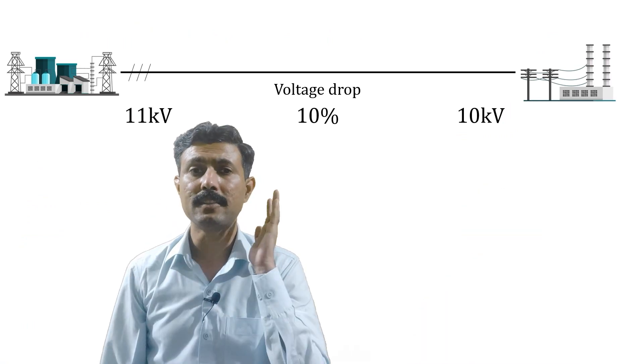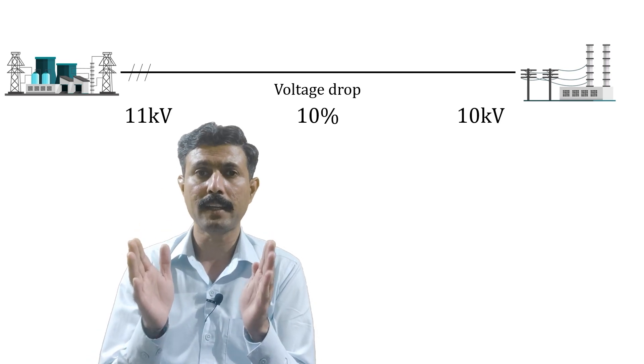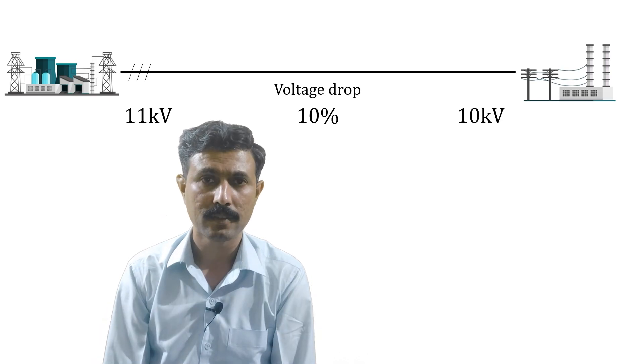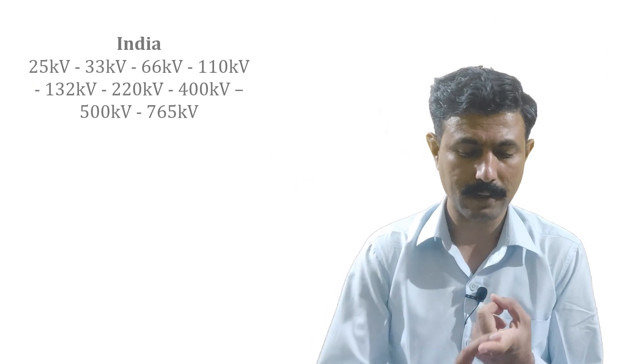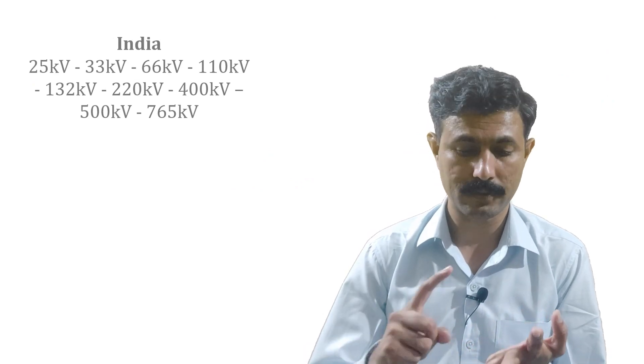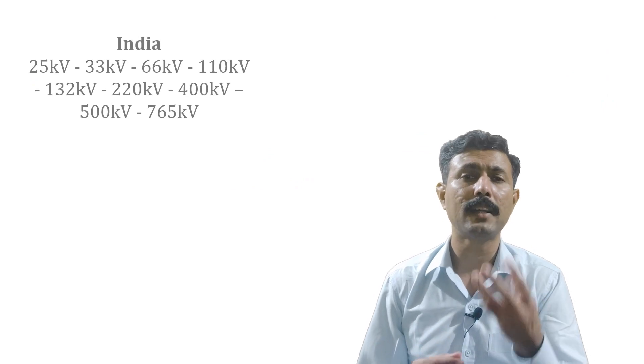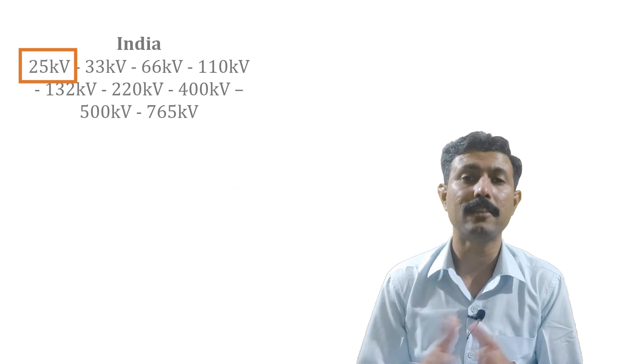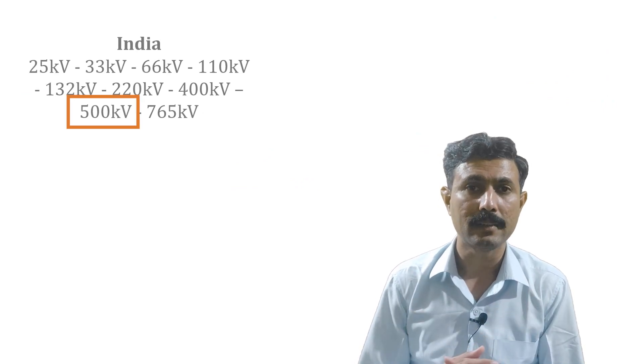So, it is not the form factor, nor the voltage drop in the line, that decides transmission line voltage. Basically, the logic that transmission voltages must be multiples of 11 kV is itself a myth — that question is wrong. I'll give you many examples where we transmit voltage not in multiples of 11. In India, we use 25 kV, 33 kV, 66 kV, 132 kV, 220 kV, 400 kV, 500 kV, and 765 kV. Many of these are not multiples of 11. We use 25 kV in Indian Railways, 500 kV HVDC lines, 765 kV.